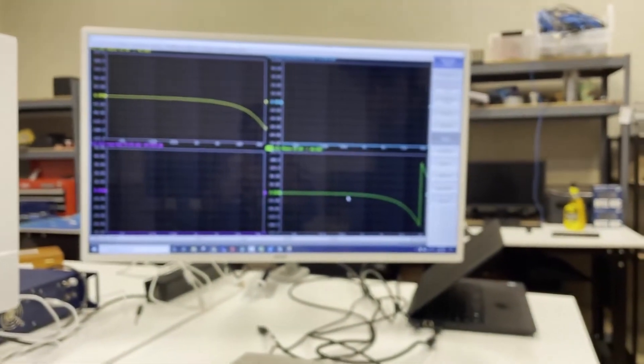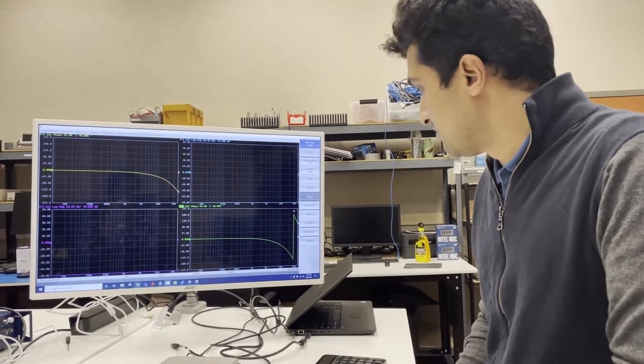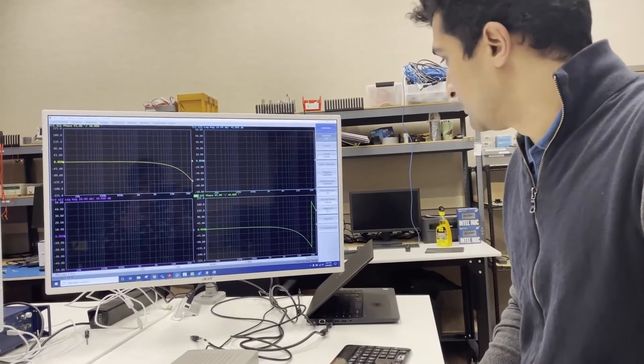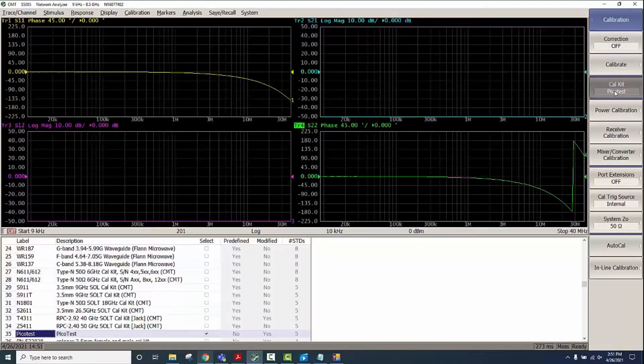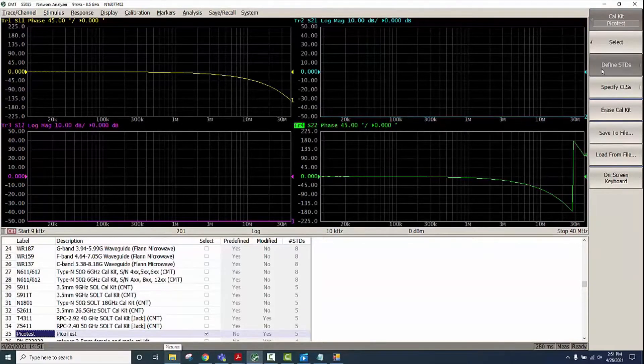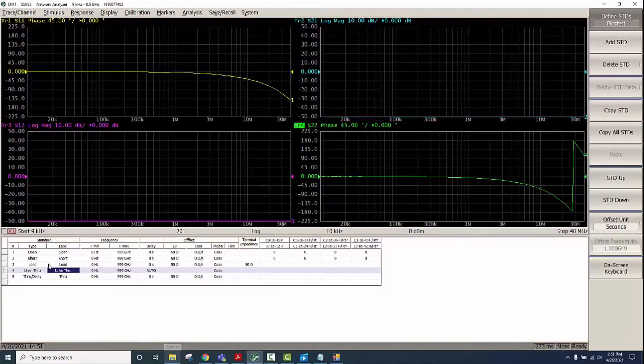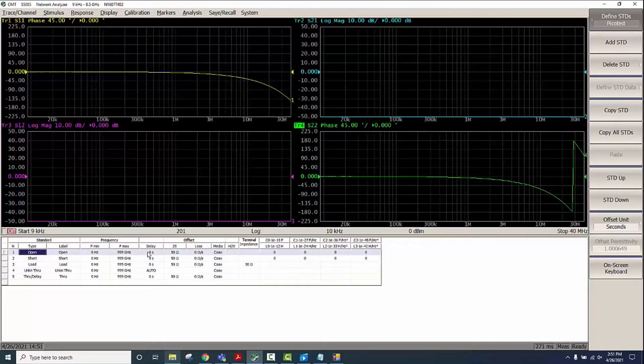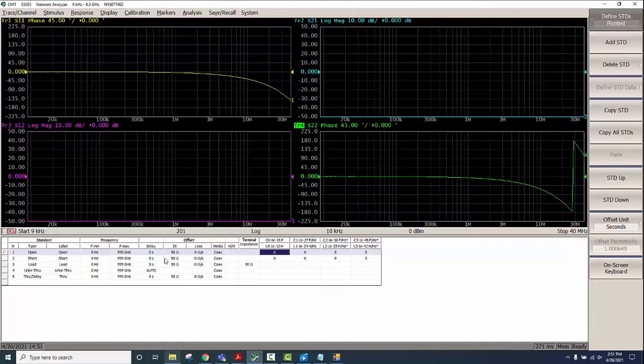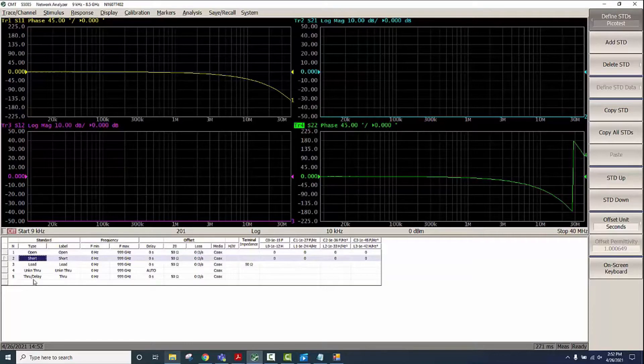Before we begin with the calibration, we will first make sure that we have the right definitions. For that we'll go to Calibration, Cal Kit, and define a cal kit. We'll go to Open and we'll consider everything to be ideal so we'll just enter it as zero all the way including the delay. Same thing for Short.